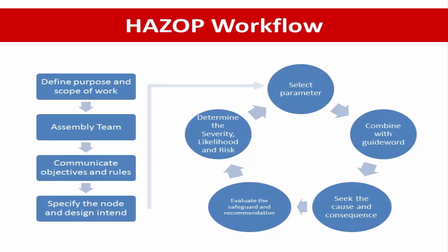Then combine this parameter with the guide word to develop a meaningful deviation — for example, combining with high, low, or less than something. Then seek the possible causes of the deviation and identify the consequences. Check the ability of existing safeguards and decide if they are adequate or if additional safeguards are necessary. Evaluate the severity without considering the presence of existing safeguards — meaning we study the maximum possible outcome. Next, evaluate the likelihood of the cause, then determine the risk of the incident.